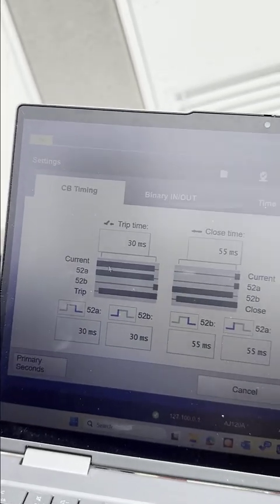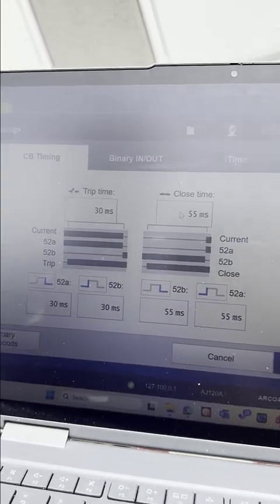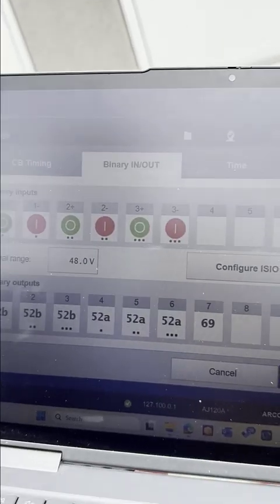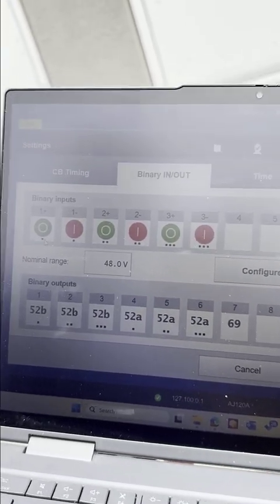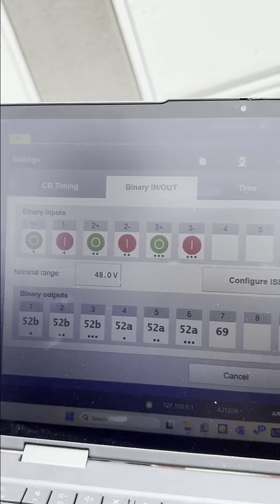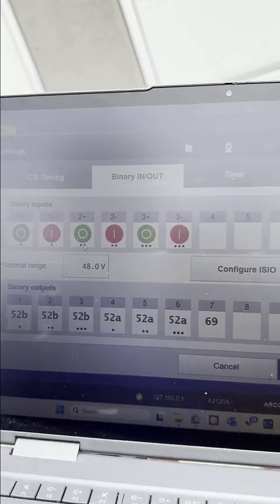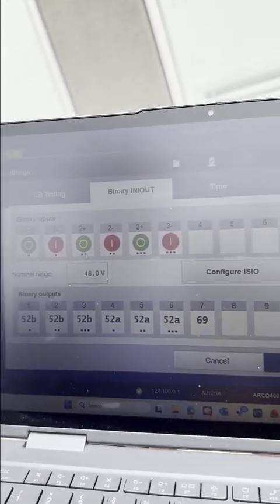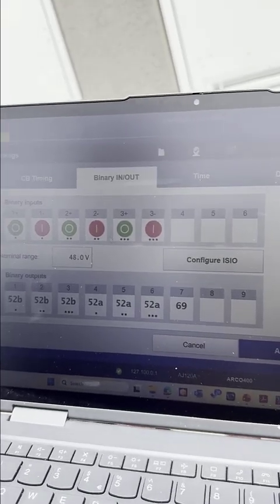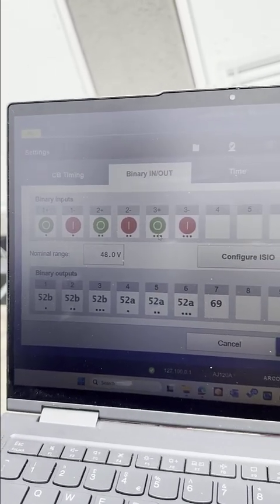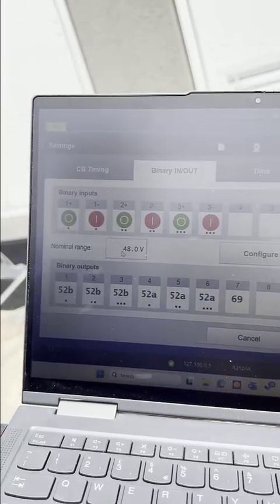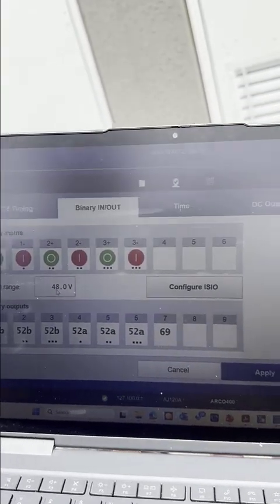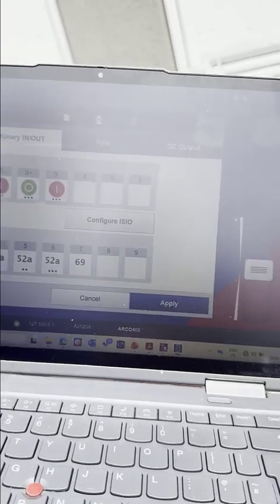Here is the setting. You can see the setting of the circuit breaker timing based on the manufacturer user manual for the trip time and the close time, also for the binary input and output, as you can see. And here is the binary input. You can see the first dot indicates L1, the second dot, if you have double dots, indicates L2 or phase B. Also 3 dots indicate L3 or phase C. Also you have to specify the nominal range here. As you can see from the nameplate of this controller box, it's 48 volt DC.